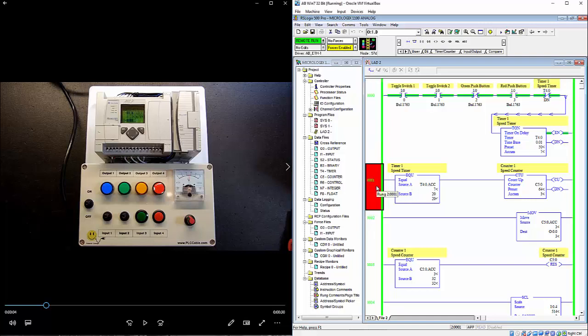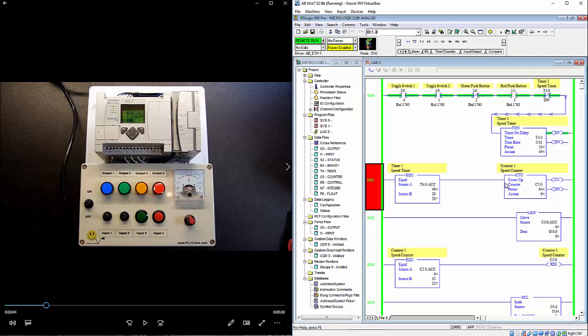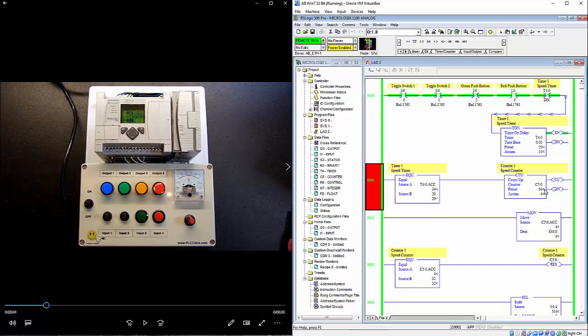So after that counts to 50, we step down here on rung one and this is an equals. So our T40, which is this one, when the accumulative value equals 20, this becomes true. And what that does, every time it hits 20, we go up on our counter. And you can barely see it ever occasionally here. It's when it goes enabled or true, it actually indexes up one. So our accumulative value down here is 13, 14, 15. And so whenever this hits 20, it counts up one. And the preset is at 64. So when this hits 64 is when the counter is going to go true.